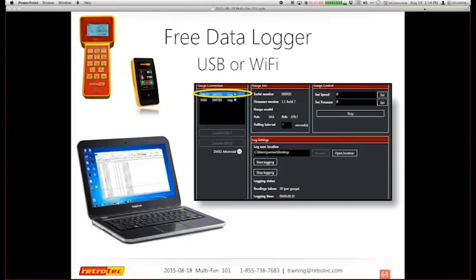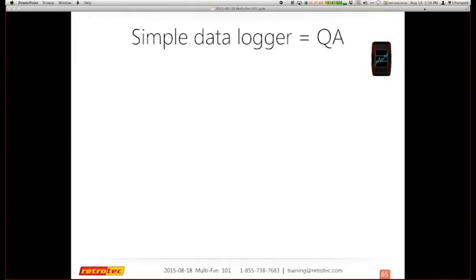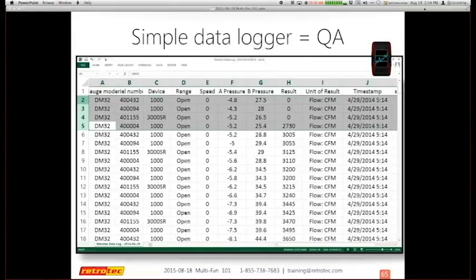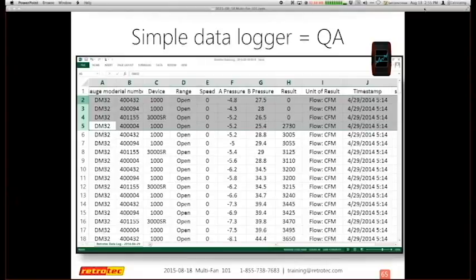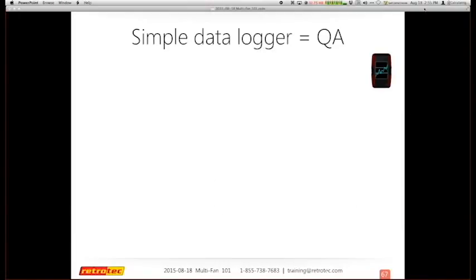There's also a free data logger that works with the DM2 and DM32. It just logs data as it runs through the gauge, can handle multiple gauges, and is a great simple tool if you just want to see the data and control the fans yourself — for example during compartmentalization testing. When done, it opens an Excel spreadsheet showing each DM32 by serial number, device type, range, pressures, and flow. It also records if you changed the range or did anything else on the gauge.